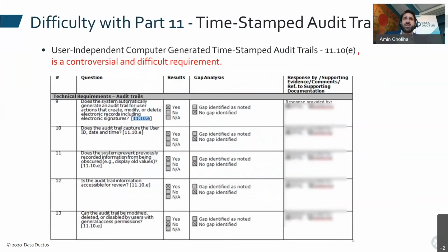I see it often, mostly with the systems that are assay systems that generate assay results. Many times they don't have proper audit trails. A proper audit trail needs to have a timestamp where the time is actually coming from a central clock, and the log also needs to be secured somehow with checksums and so on, so you can see the integrity of the audit log.